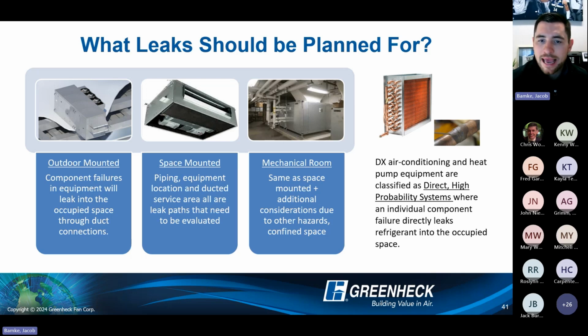And then lastly, that mechanical room, it's the same as your space mounted, but there are additional considerations due to the confined space that unit would be installed in. So there are some other hazards that could come along with a mildly flammable refrigerant in those small spaces with such a big charge.